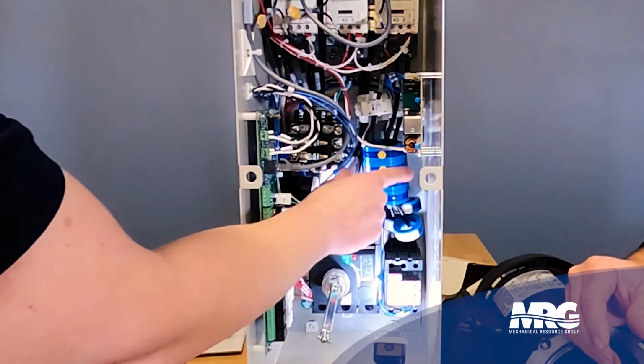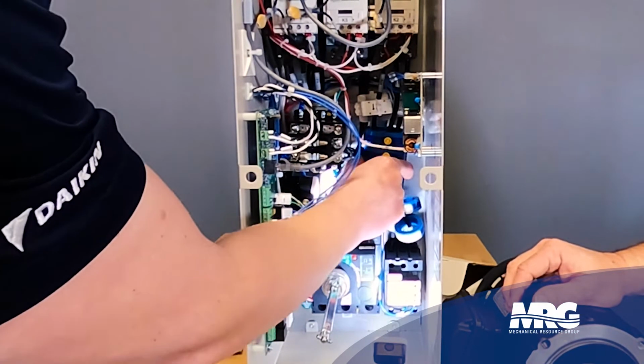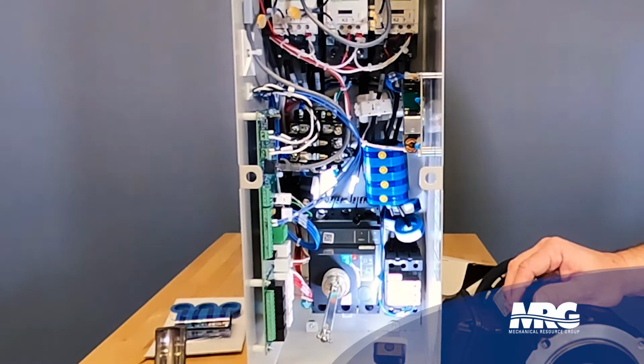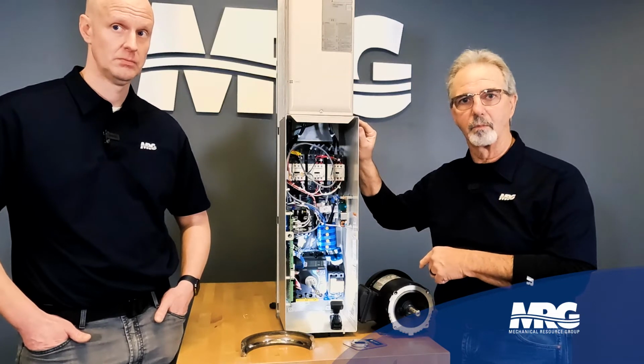And what it does is it's just like what you would have like a current transformer. Okay. And so what we do is when we capture that, we hold it there, and then when we collapse the field, it dissipates naturally. Okay. What we have is we have it installed on this drive. Now this drive here has a bypass on it, but what I need to explain is that the variable frequency portion of it, these mount between the output of the drive and the input of the motor.